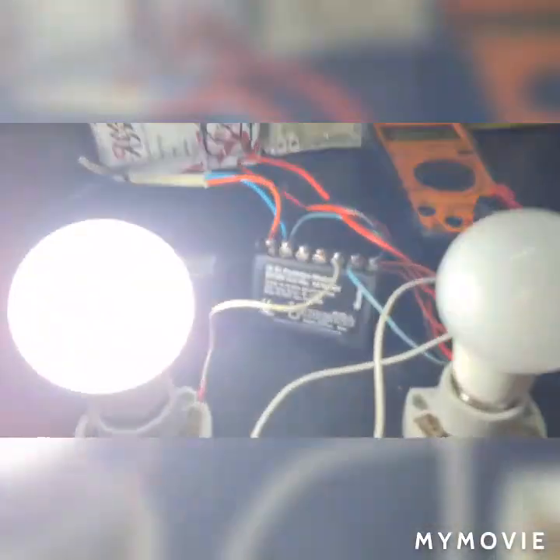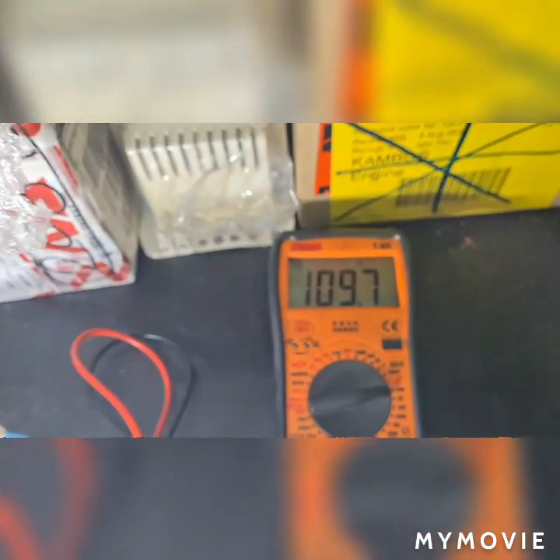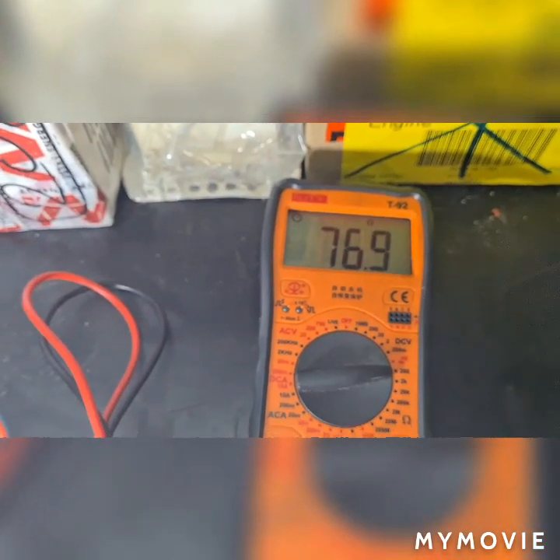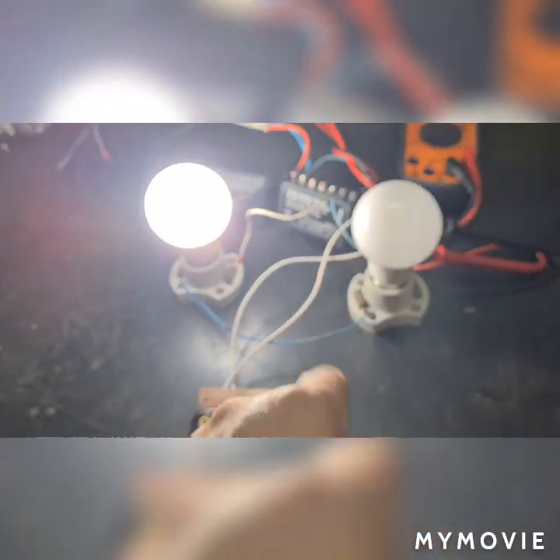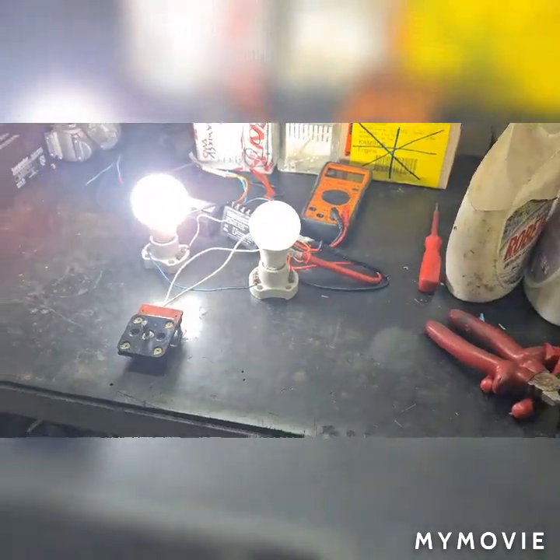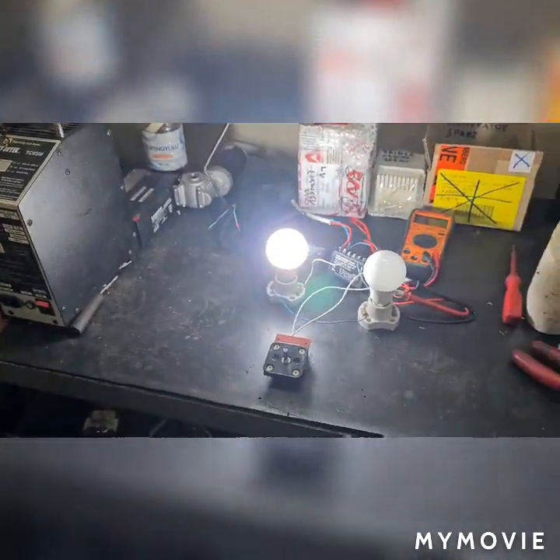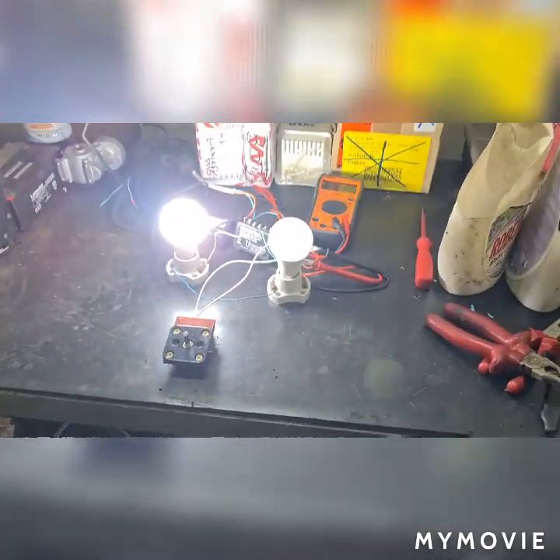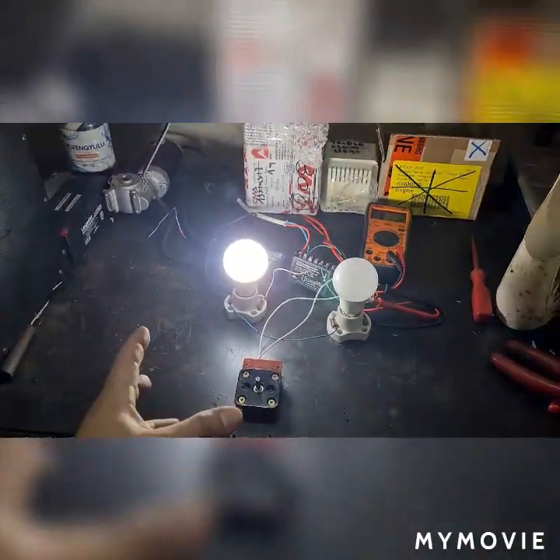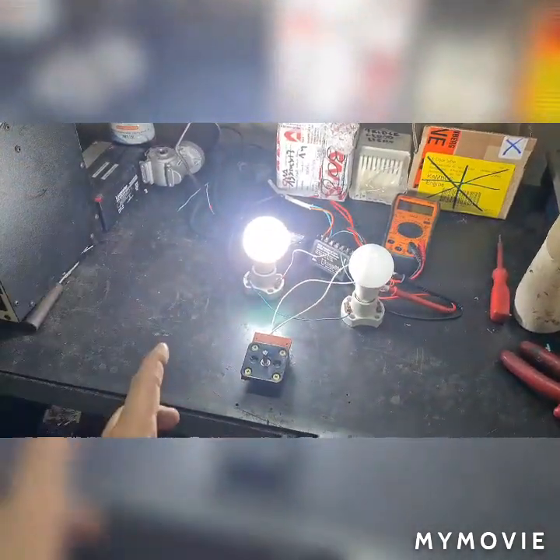Then I'm going to lower the resistance of my potentiometer from 109 to 0 ohms, and as you may notice here, from 109 ohms going to the 0 ohm value, the terminal number 11 and 12 is still in close connection, and 11 and 14 is in open connection. So I don't have lights on our right side, and I have light on the left side. This is how the motor protector relay is operated.